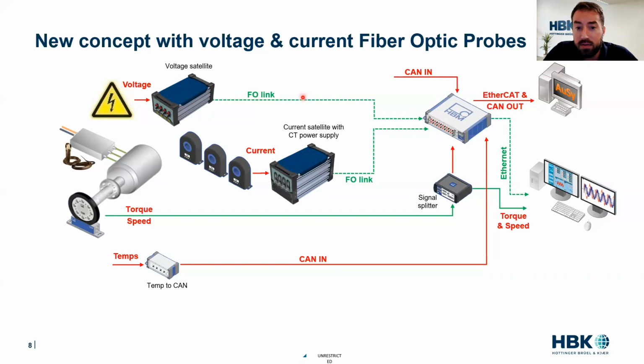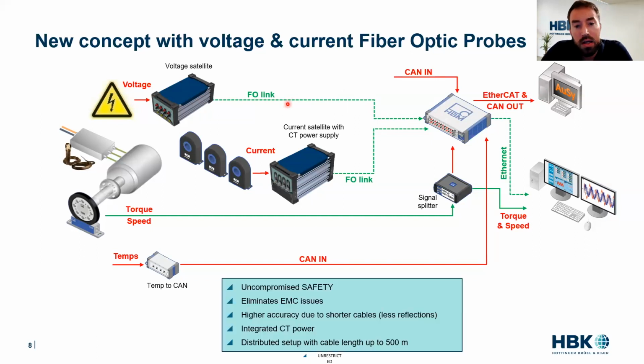That measurement is then sent over fiber optic, so it's completely safe—really the safest measurement you can get—resulting in super high quality. We're extremely excited about this. It was really made for the aerospace industry, with uncompromised safety because you don't have high voltages getting back to the measurement unit, to people, or to computers. The short cables effectively eliminate a lot of EMC issues, which we'll talk about in a moment.